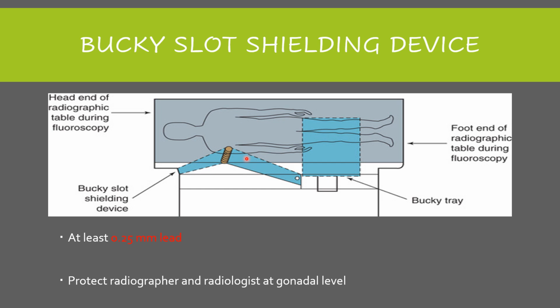Bucky slot cover is right here. It's at least 0.25 millimeters of lead. So as you slide the image receptor down towards the feet, this Bucky slot cover folds from inside and covers this area right here. It protects the radiographer and radiologist at gonadal level.